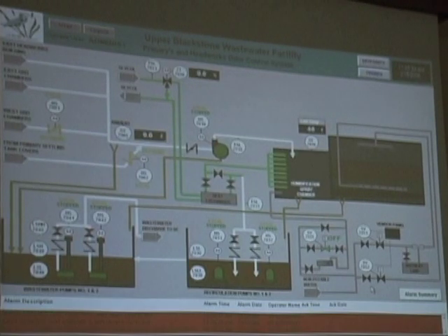If for whatever reason that communication line goes down, that's all it is, it's just reading that drive. It's talking to that drive back and forth. If you no longer can talk to that drive, you don't know what that drive is doing. If you try and tell it to start and you have no comms, obviously it can't start because you're not actually sending it the command.